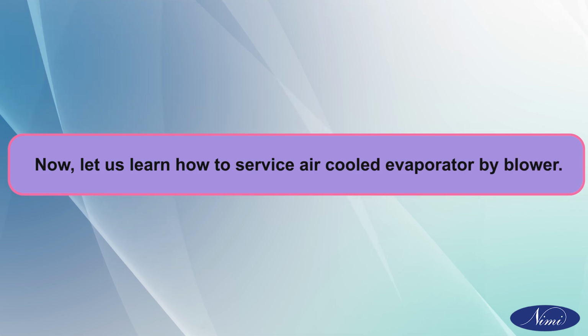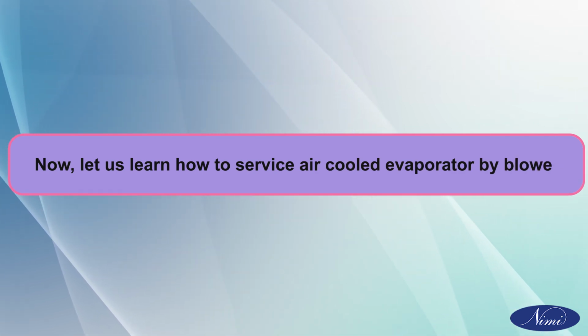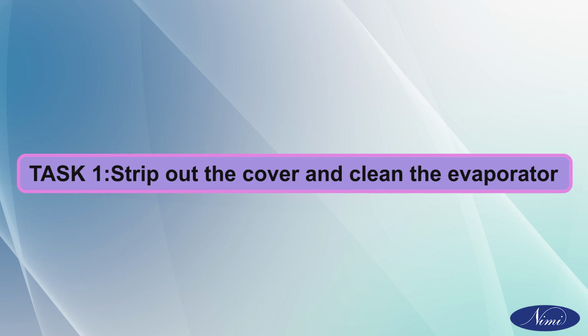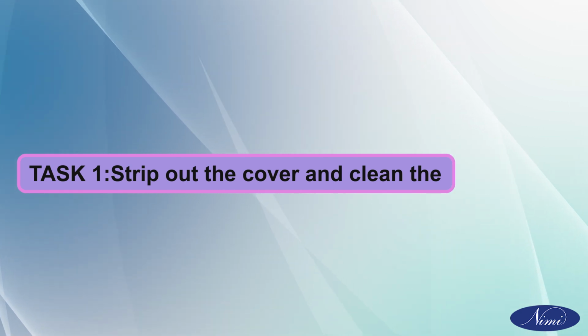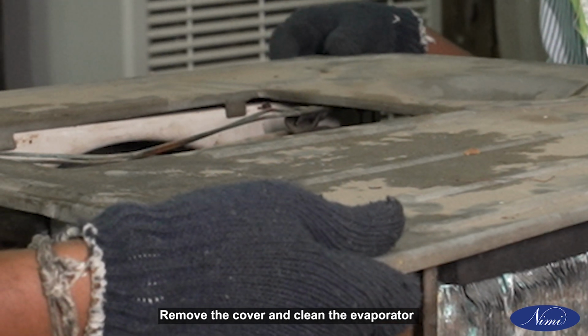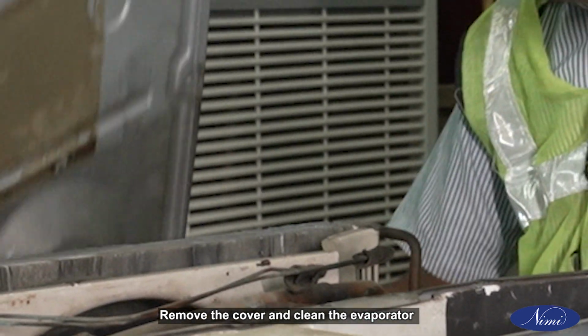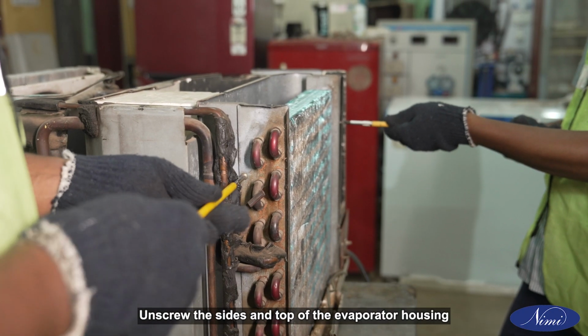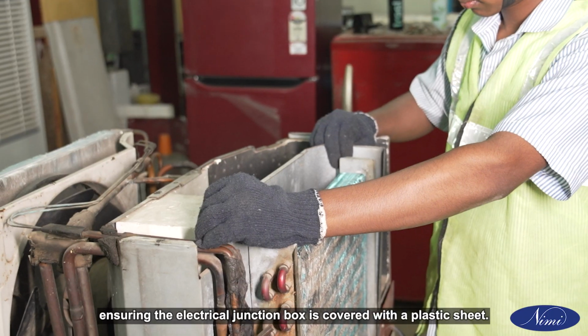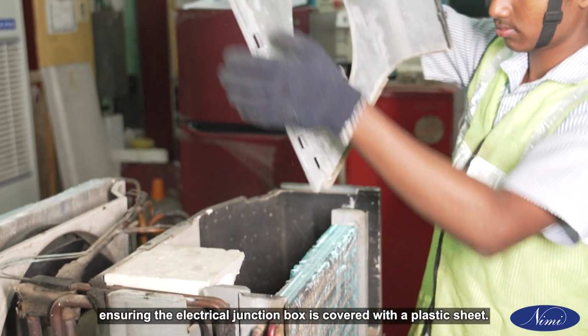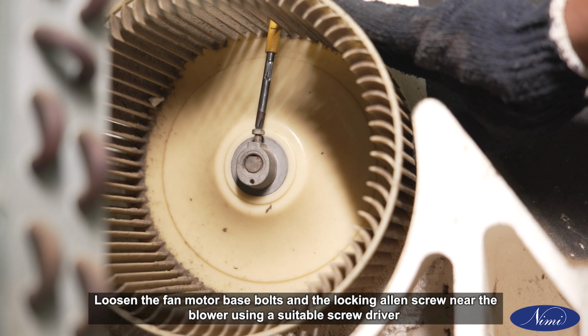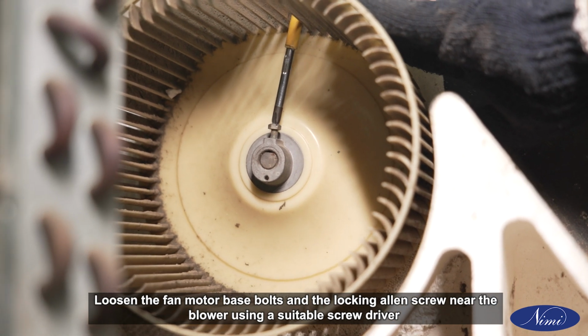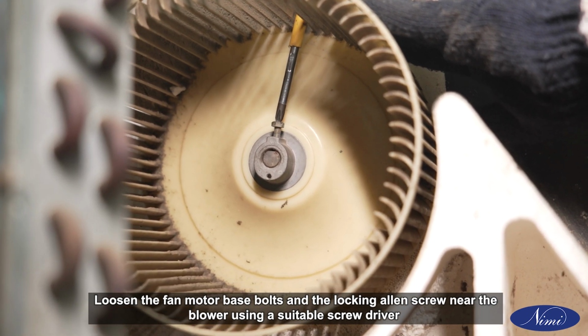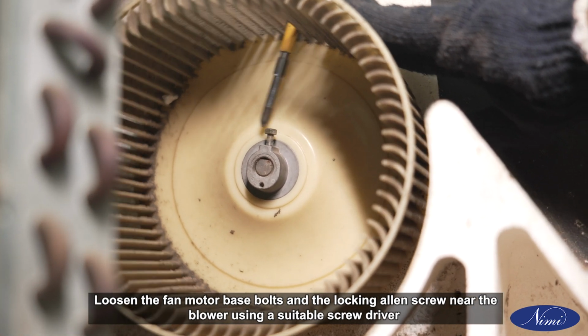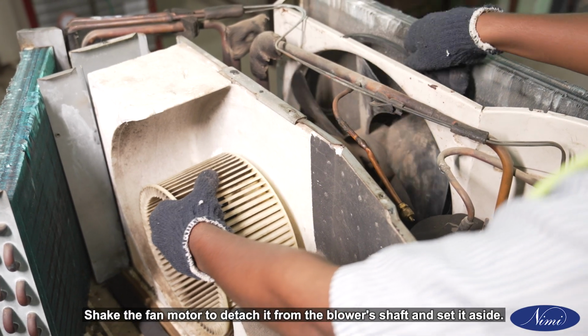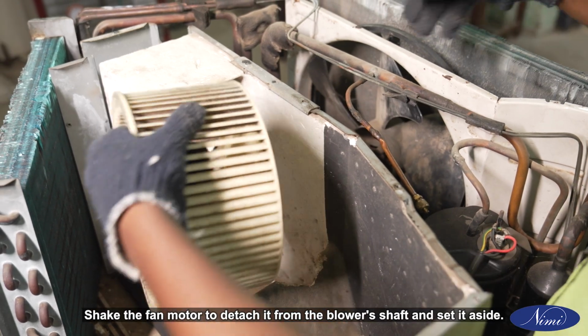Now, let us learn how to service air-cooled evaporator by blower. Task 1. Strip out the cover and clean the evaporator. Remove the cover and clean the evaporator. Unscrew the sides and top of the evaporator housing, ensuring the electrical junction box is covered with a plastic sheet. Loosen the fan motor base bolts and the locking Allen screw near the blower using a suitable screwdriver. Shake the fan motor to detach it from the blower's shaft and set it aside.